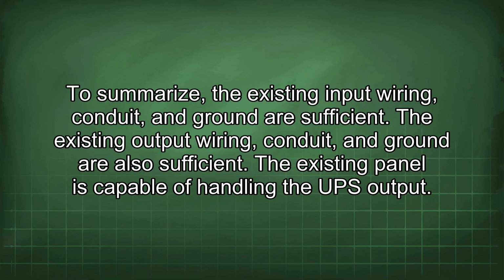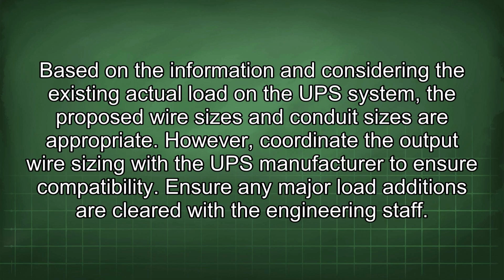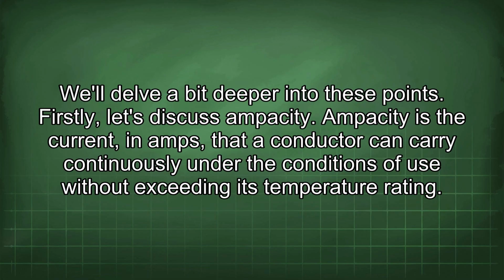To summarize, the existing input wiring, conduit, and ground are sufficient. The existing output wiring, conduit, and ground are also sufficient. The existing panel is capable of handling the UPS output. Based on the information and considering the existing actual load in the UPS system, the proposed wire sizes and conduit sizes are appropriate. However, coordinate the output wire sizing with the UPS manufacturer to ensure compatibility. Ensure any major load additions are cleared with the engineering staff. We'll delve a bit deeper into these points.